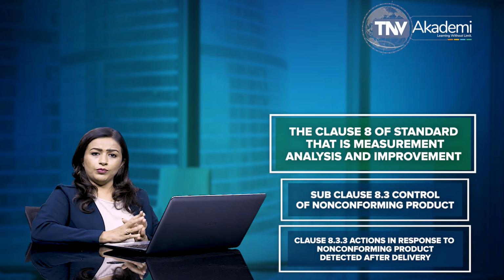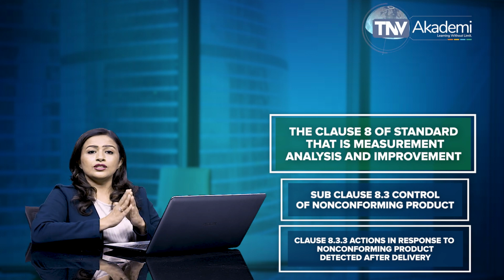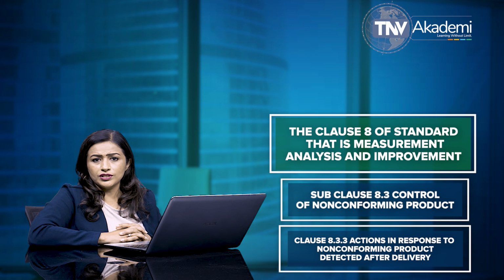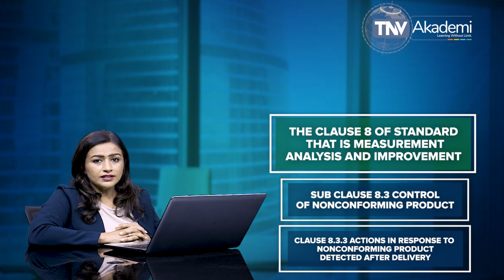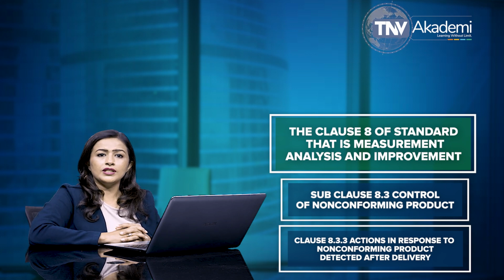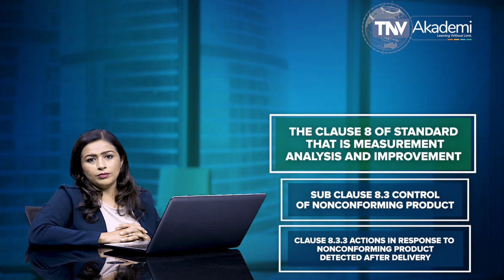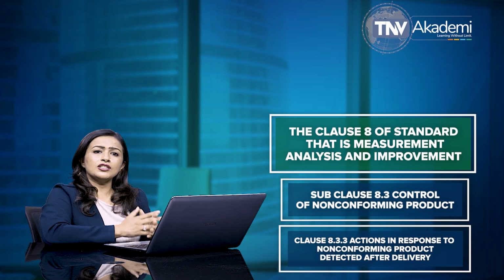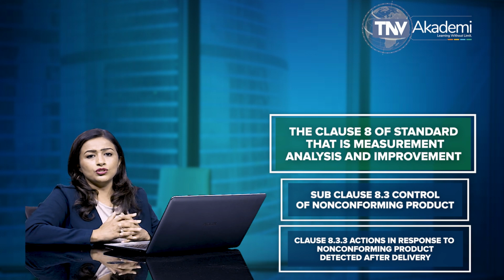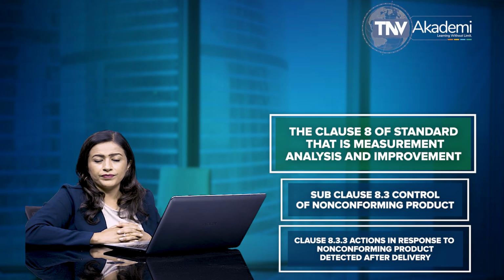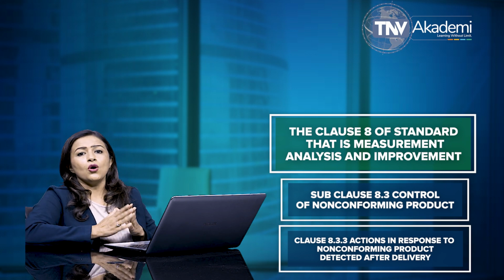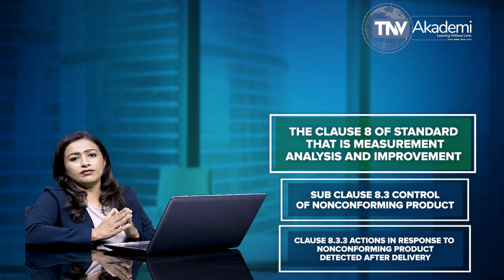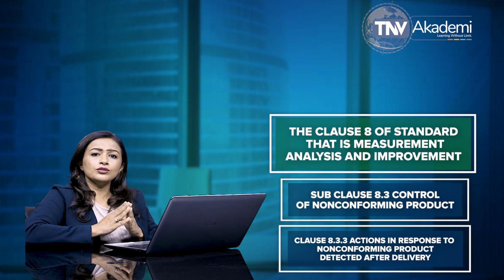The subclause 8.3.3 states that the organization must document procedures for issuing advisory notices in accordance with applicable regulatory requirements. These procedures must be capable of being put into effect at any time. According to this subclause, organization is required to maintain records of actions relating to the issuance of advisory notices.